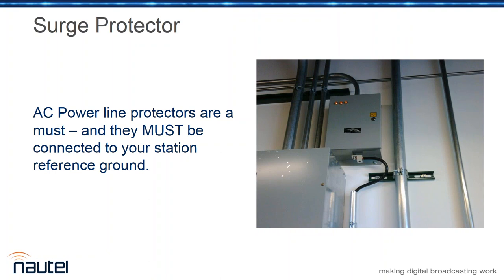Now you'll notice on this one, again, what's wrong with this picture? The ground wire is run in a conduit. Conduit makes a really good shield, it's basically a ferroresonant type thing, the same as putting a ferrite on the ground lead and making it into an inductance. We don't want that. A ground wire should run straight to the reference ground point. If you have to, for a local code, run it through some sort of conduit, I'd use a PVC conduit or flex or something that has very little shielding property.